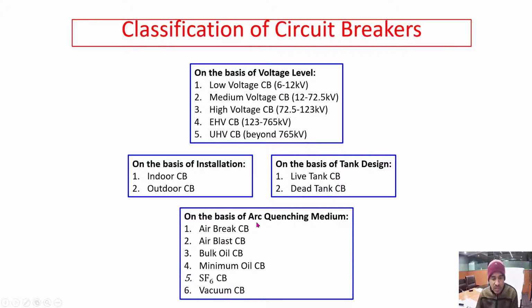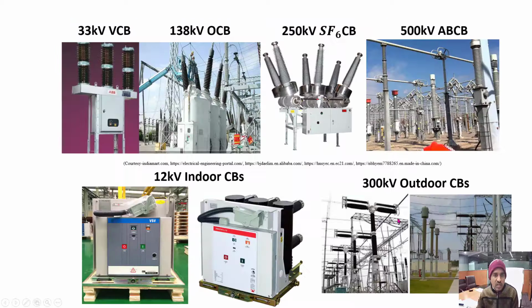The next one is on the basis of arc quenching medium. There is a requirement for quenching the arc which appears inside the circuit breaker when we break the circuit. But arc quenching mediums are different for different circuit breakers. So on that basis also circuit breakers can be classified. That is air break circuit breaker, air blast circuit breaker, bulk oil circuit breaker, minimum oil circuit breaker, SF6 circuit breaker, and vacuum circuit breaker. So these are the several circuit breakers.